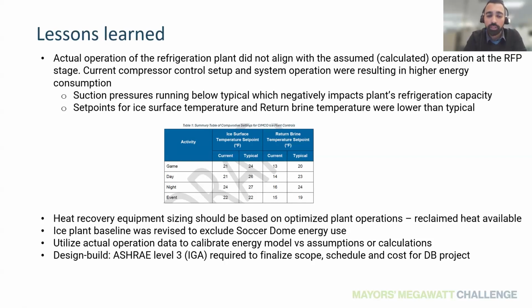Going forward, when we change the setting back to the typical suction pressure, around 24 psi, the expectation is the compressors will run for less time, which also correlates to the finding that we don't have enough waste heat energy to supplement all the HVAC or other system needs in the building. Some of these findings came about after the detailed investment grade audit was performed.